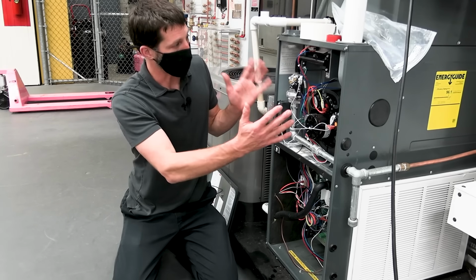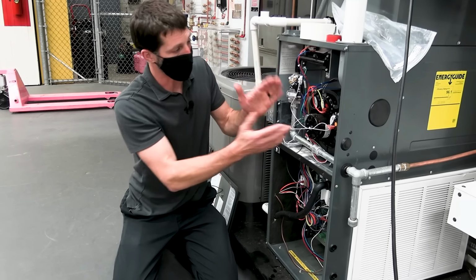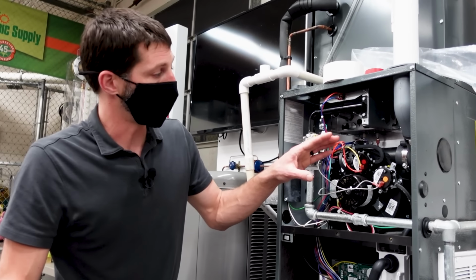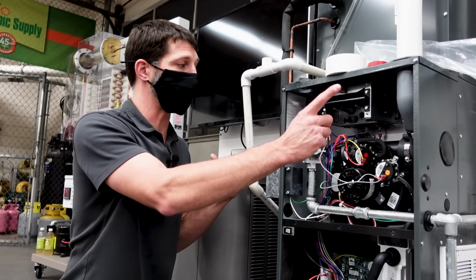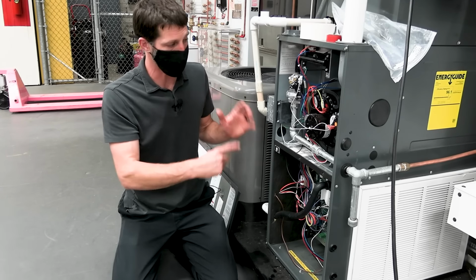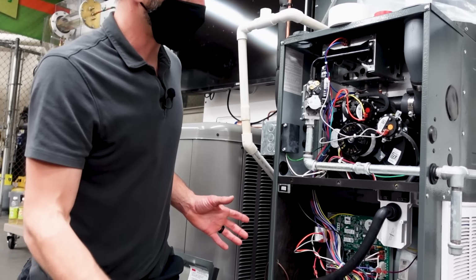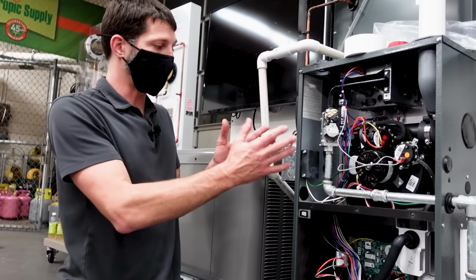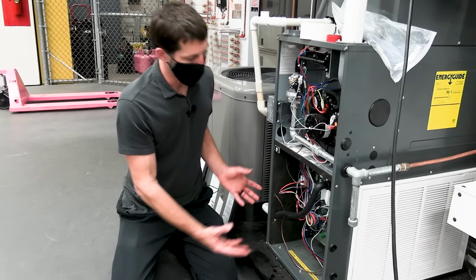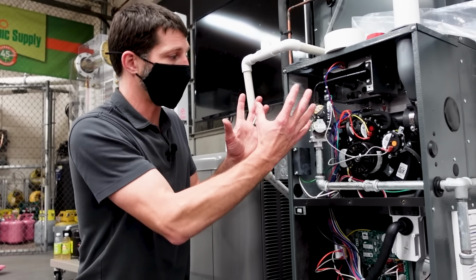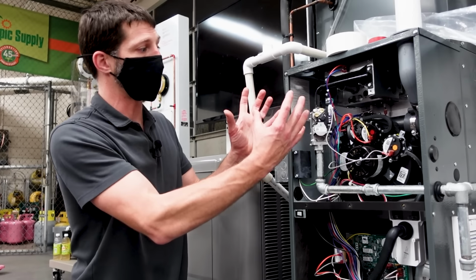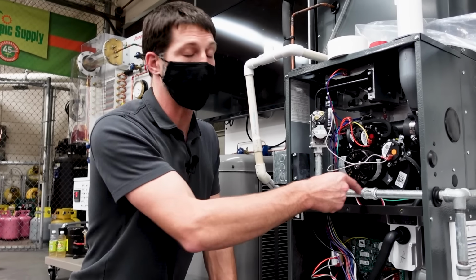It's gaining that from the heat exchange of the air, but mainly from the flame process. And so the secondary heat exchanger, you have water that's traveling through that heat exchanger, and you are able to transfer that heat that's still within the water as it's traveling through there. It's able to get moved basically into the air, and so the air is absorbing that heat from the condensate in the secondary heat exchanger.